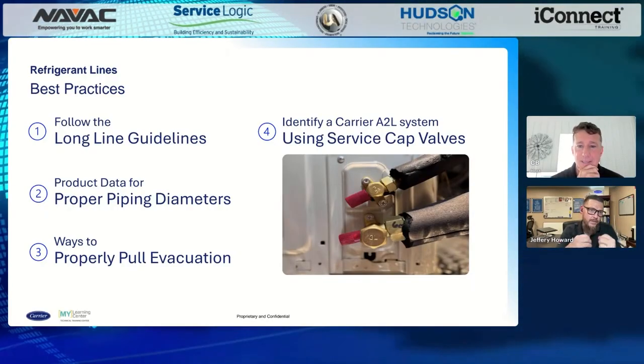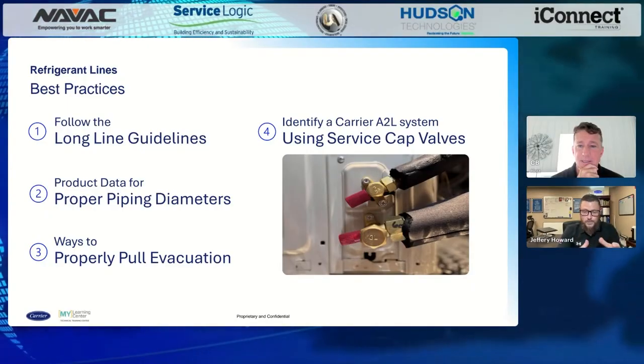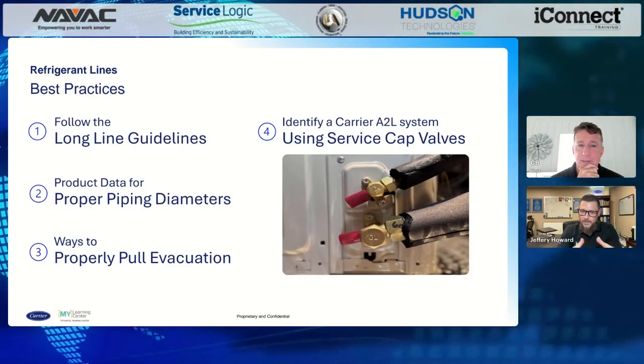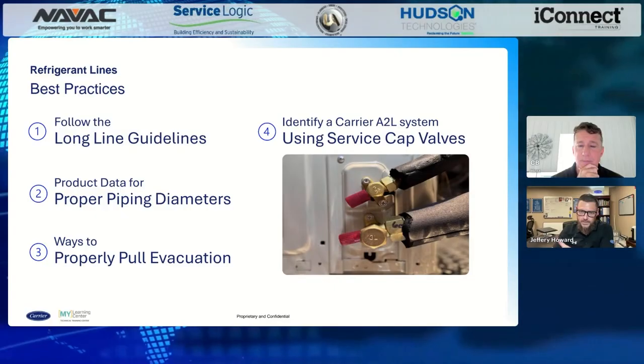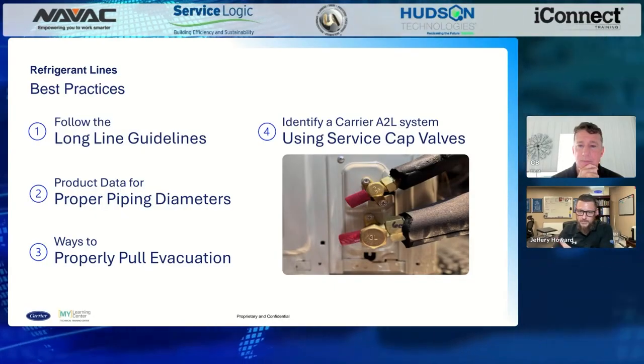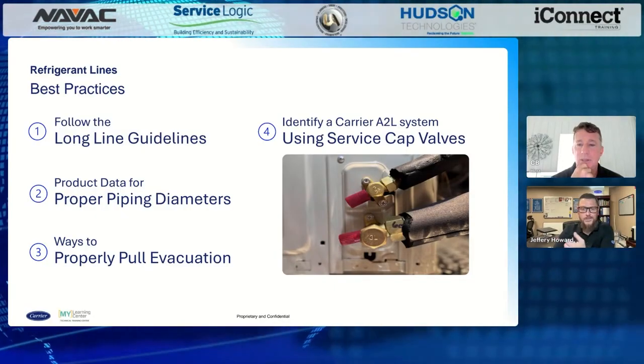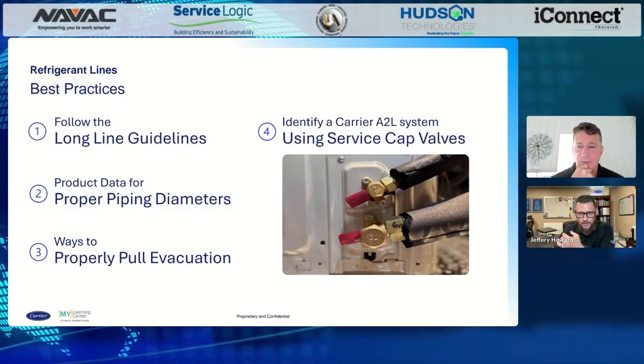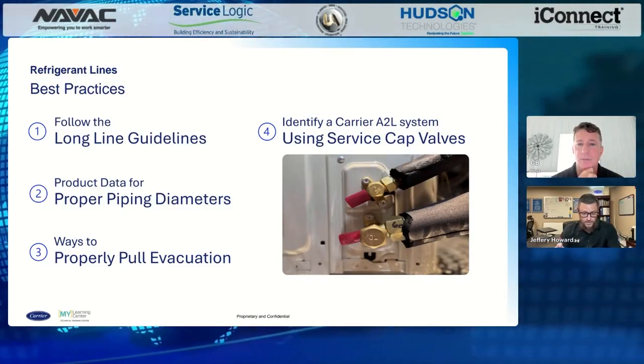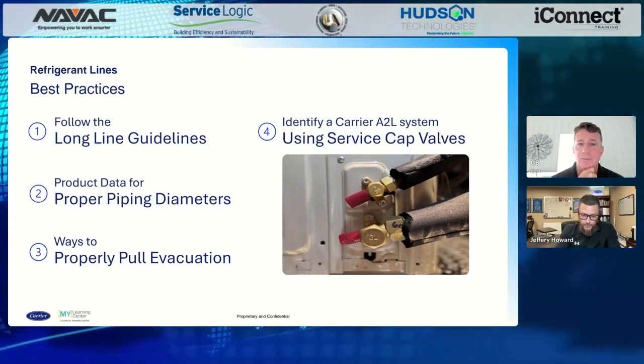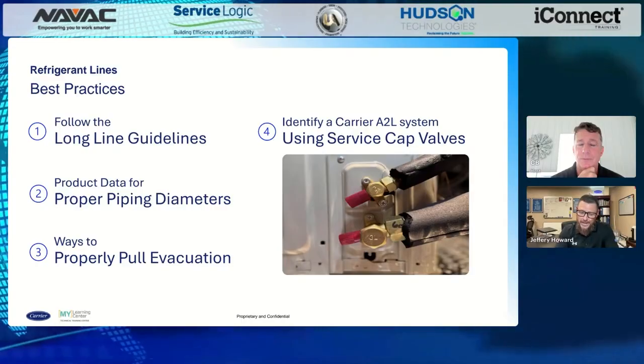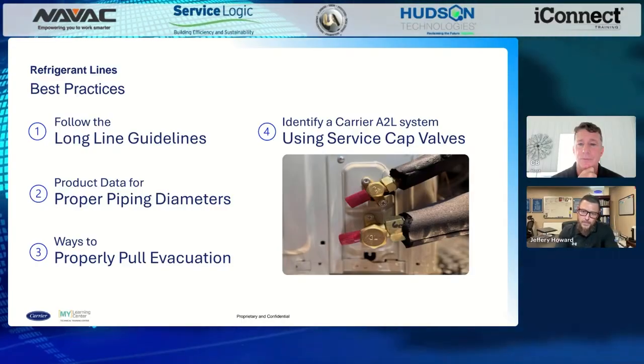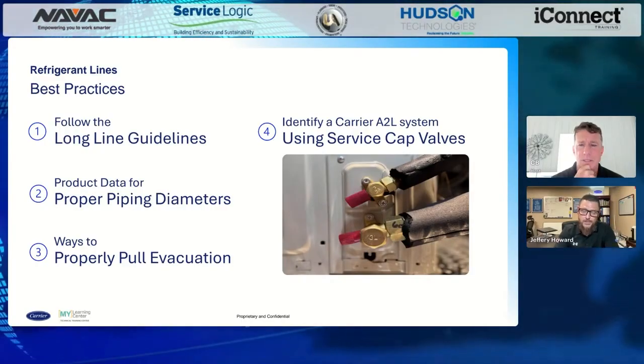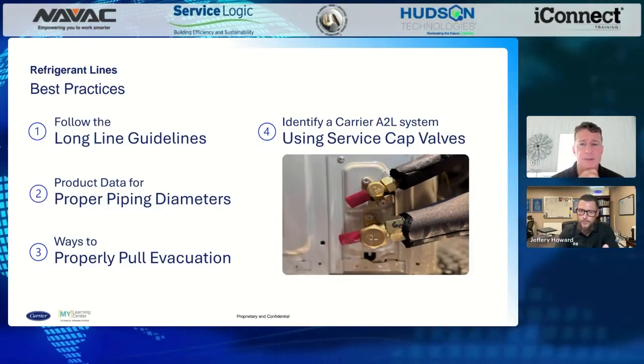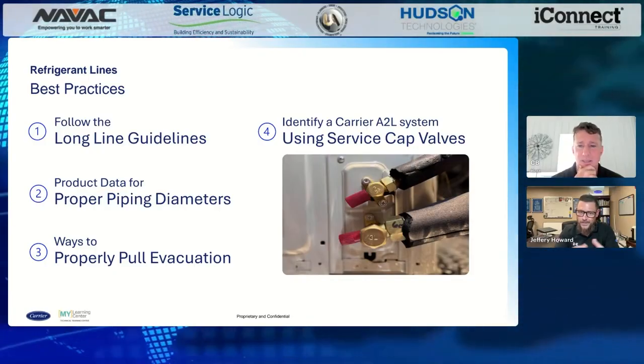So what happens if I have a 3/4 inch service valve? Does that mean I have to put in a 3/4 inch line set on my suction side? Well, not necessarily. It depends on the length of the line. It depends on other things too. But what happens if I make it smaller? What happens if I put a 5/8 inch line in versus a 3/4? How does it change your capacity? Well, you're looking at length and capacity.